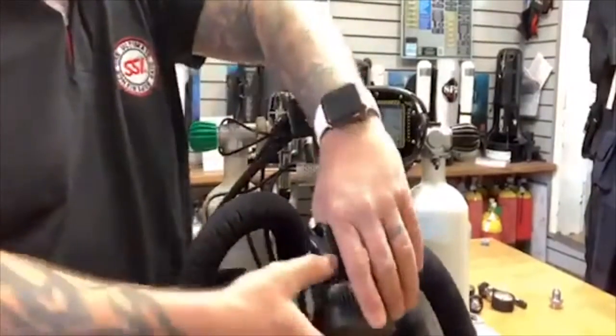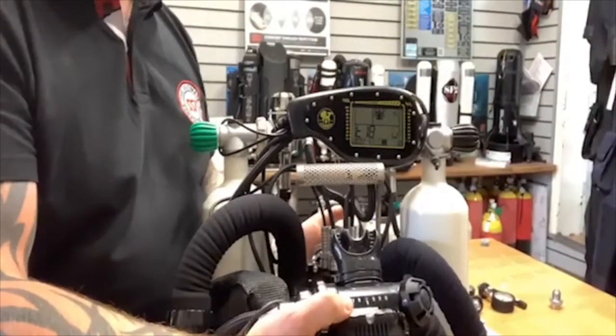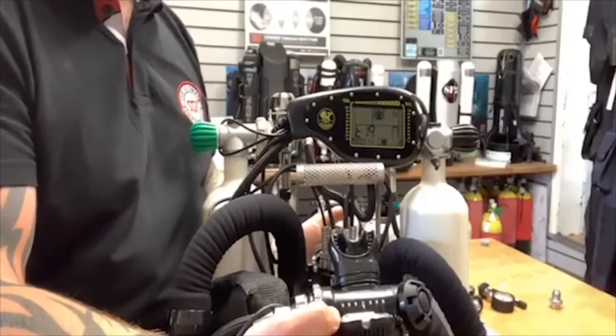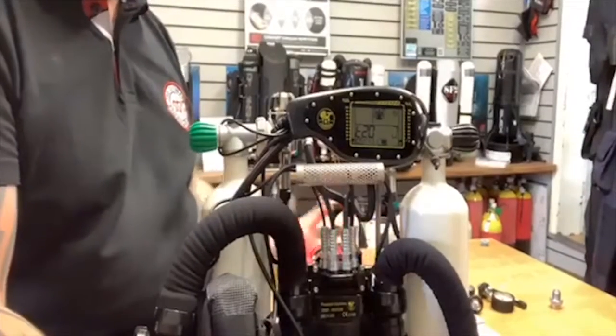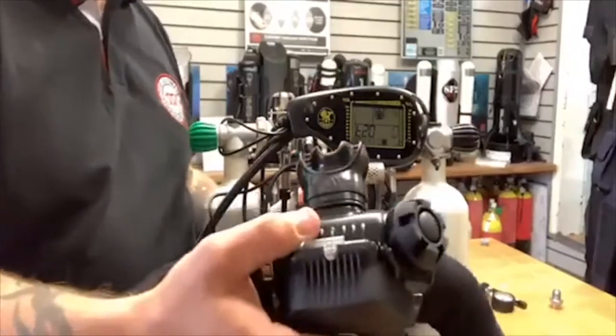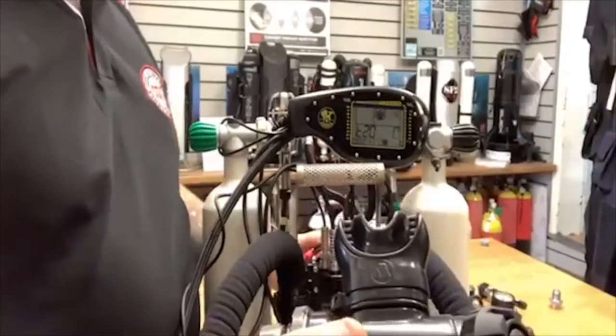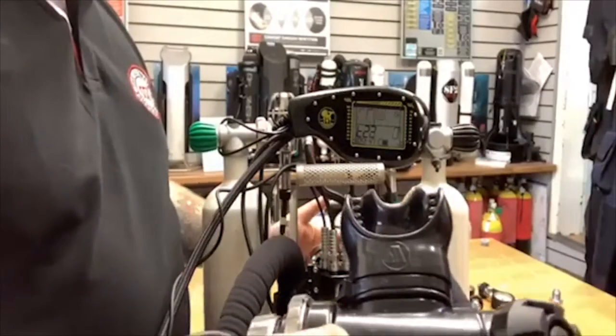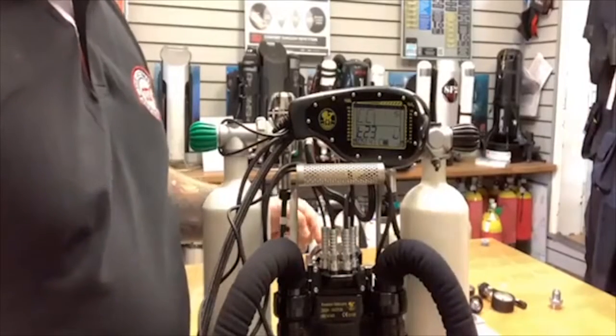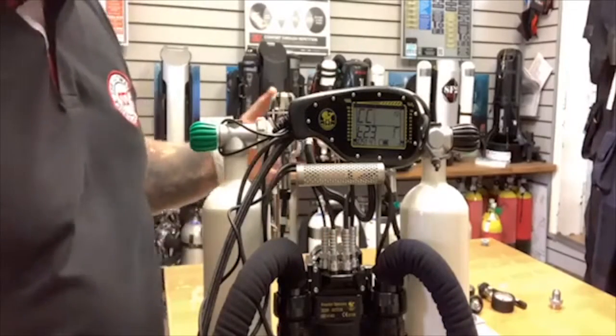So if we're going to look at the hood, there's the backlight. So that's the backlight test 17, test 18. Red on the hood, look. Green on the hood now. Red on the back, you see my hand through the back there. Then, in a minute, the hood's going to vibrate. You might be able to hear it. And now, beep, beep, beep. That's our alarm, checking our alarm's working at the back.